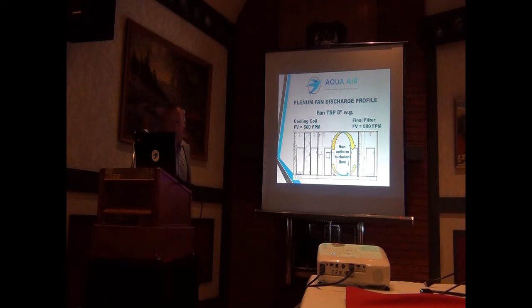But as you can see here, this fan is spinning and it's pressurizing this area, so it's really a turbulent spinning blender type situation in there. So it pressurizes this section, and then really physics does the rest. Air wants to move from high pressure to low pressure. It's lower pressure on this side. It's going to travel through that filter.